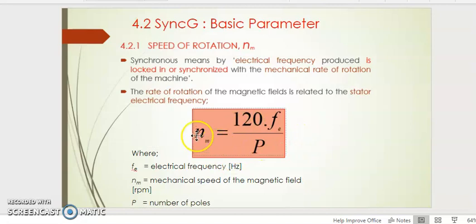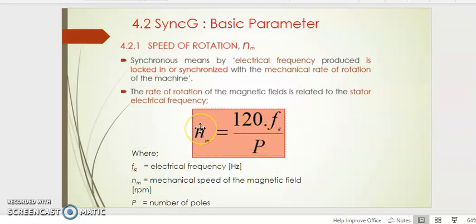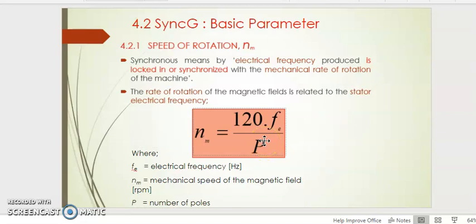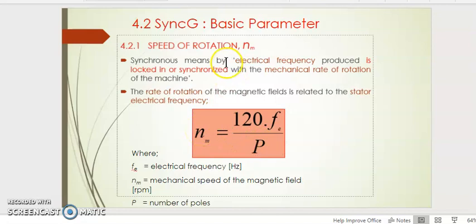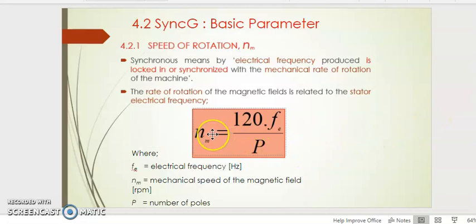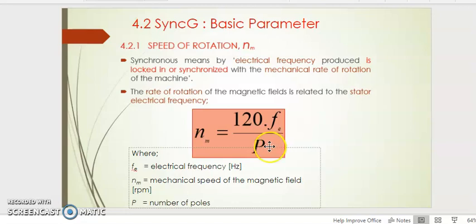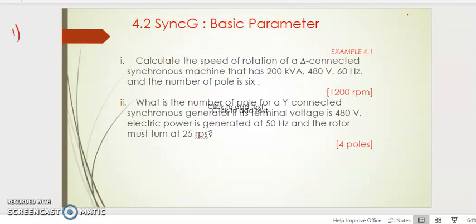That is why it is called a synchronous motor. The governing formula is: mechanical rotation Nm is equal to 120 times electrical frequency fe divided by number of poles. The higher the number of poles, the lower the mechanical speed of the shaft. The least number of poles is two. We can have more poles such that the generator needs only a few turns of the shaft to produce the magnetic field voltage. We need low rotation speed to produce the voltage output with a higher pole construction.